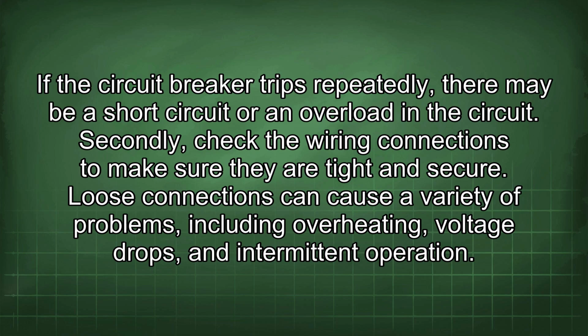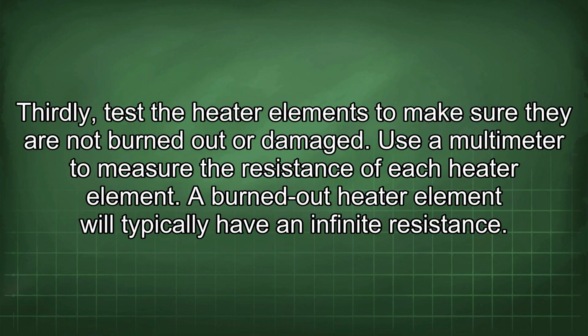Secondly, check the wiring connections to make sure they are tight and secure. Loose connections can cause a variety of problems, including overheating, voltage drops, and intermittent operation. Thirdly, test the heater elements to make sure they are not burned out or damaged. Use a multimeter to measure the resistance of each heater element. A burned-out heater element will typically have an infinite resistance.